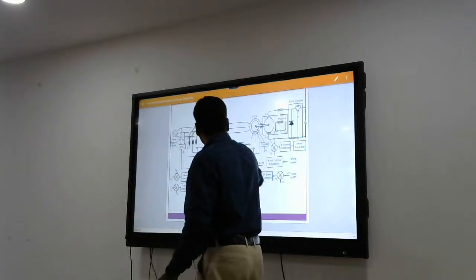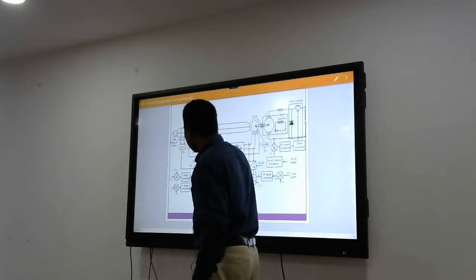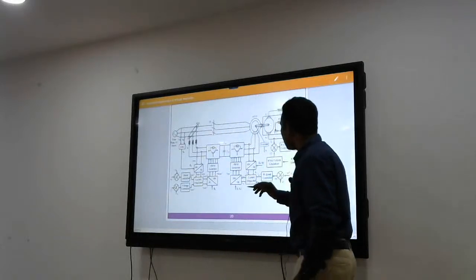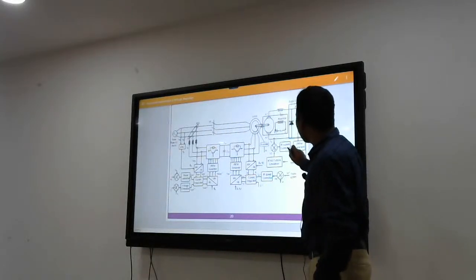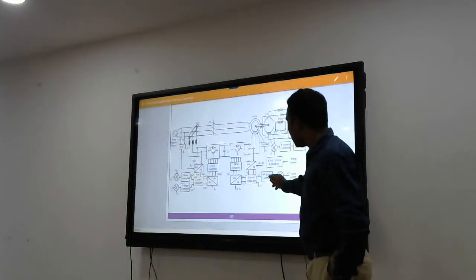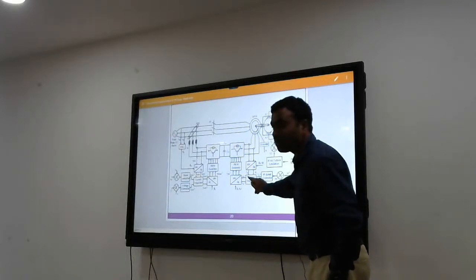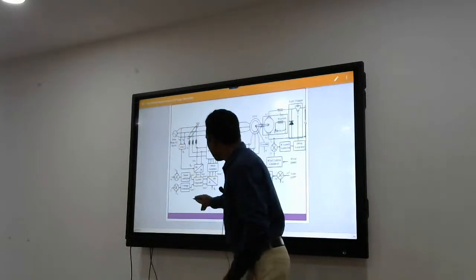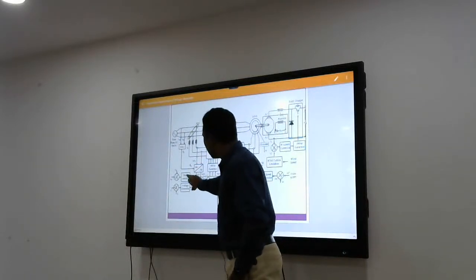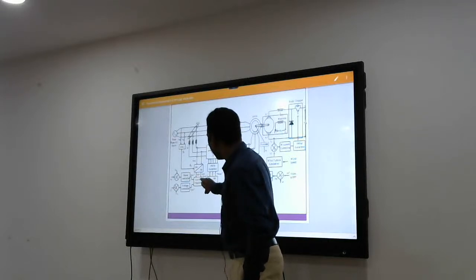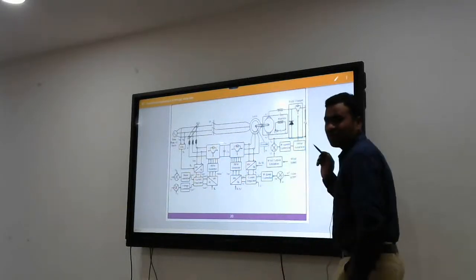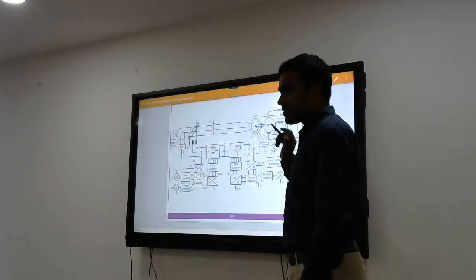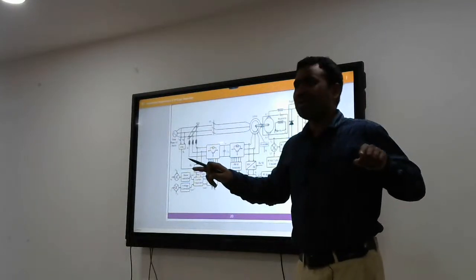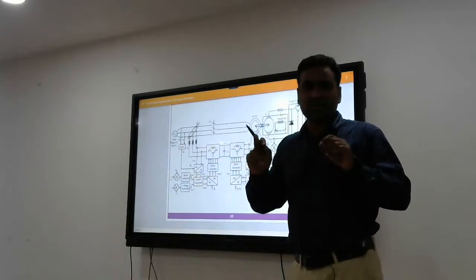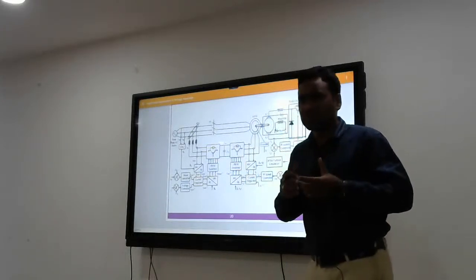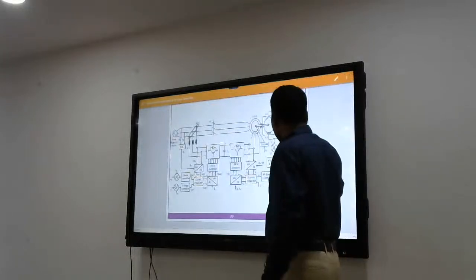Now, one more thing here is, this is to maintain the DC link voltage. This is the converter control. And if you see here, there is one PI controller, another second PI controller. Here you have two PI controllers, 2 plus 2, 4. Here you have one PI controller, 5. Here you have one PI controller, 6. You have two PI controllers inside. In total there are 8 PI controllers to control this DFIG system. You have to properly tune those PI controllers, and you have to place the digital signals to achieve this.